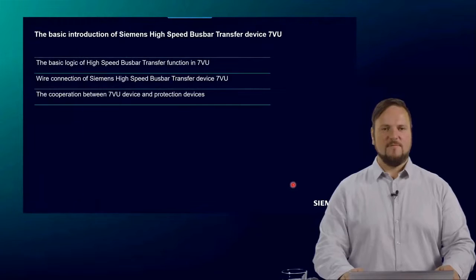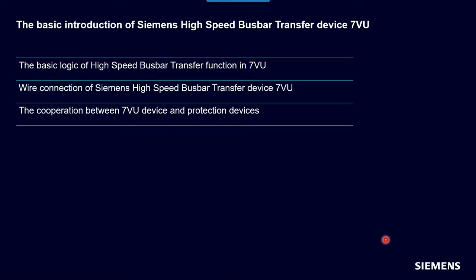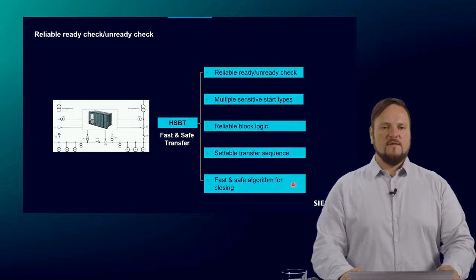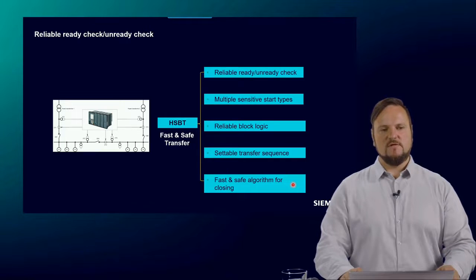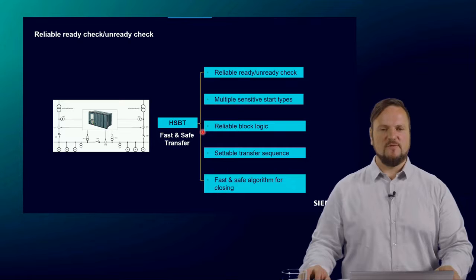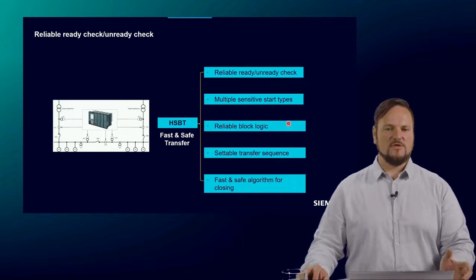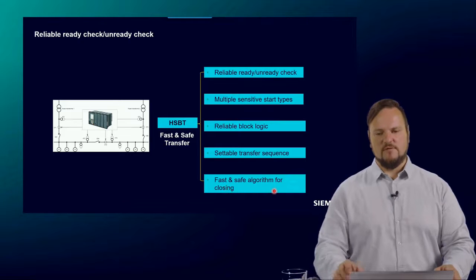Coming to the second part of my presentation — the basic introduction of an HSBT system. I will explain the basic logic, then the wiring connection, and finally one slide regarding the cooperation between the 7VU85 device and protection devices. The structure of the HSBT system includes the HSBT functionality itself, split into: a reliability check for readiness and unreadiness, multiple sensitive start types, a blocking logic check, the transfer sequence setting, and finally the fast and safe algorithm for closing the breaker.